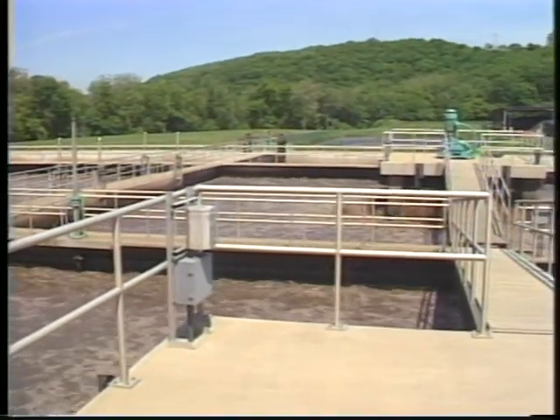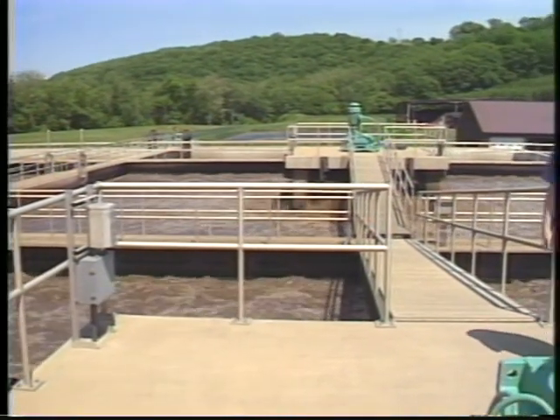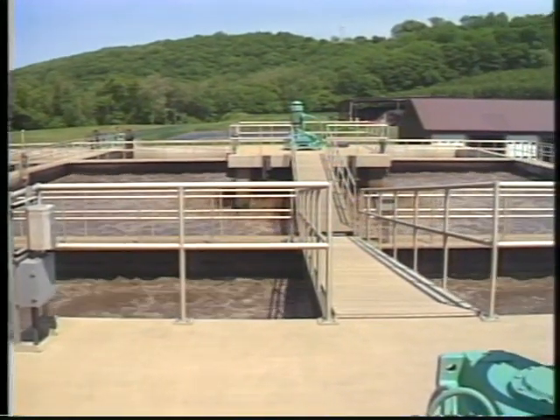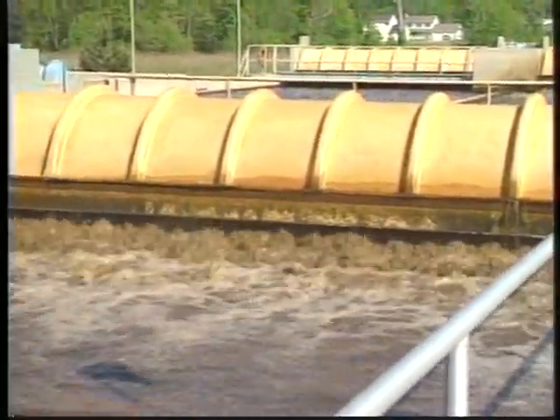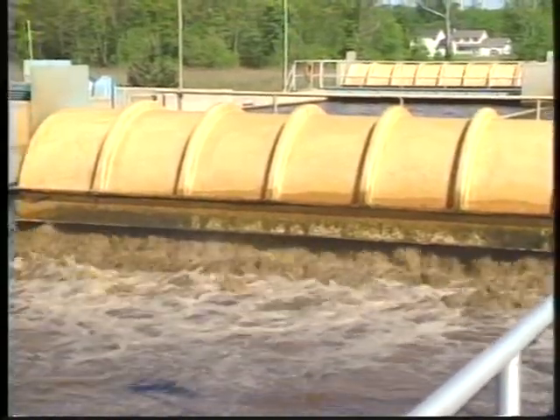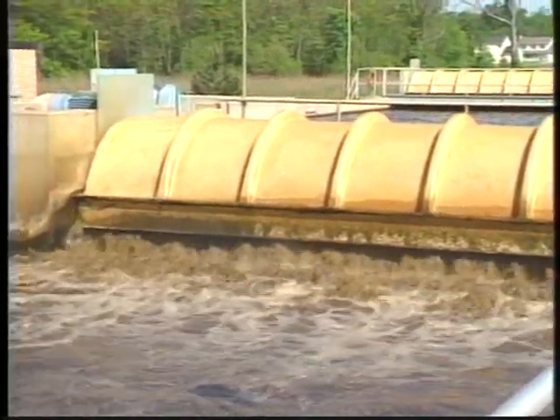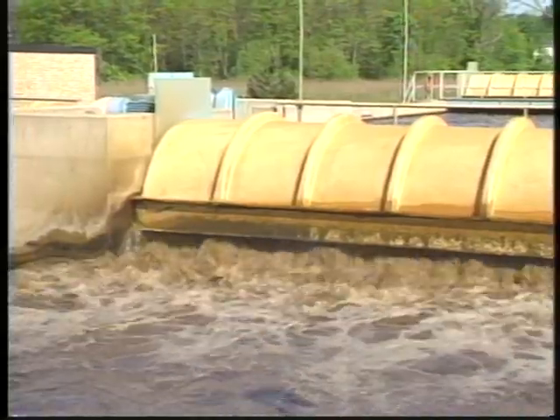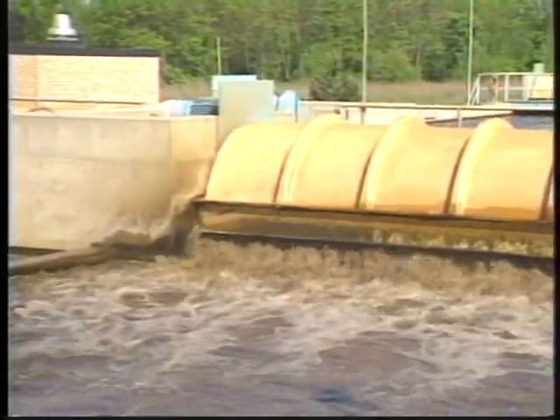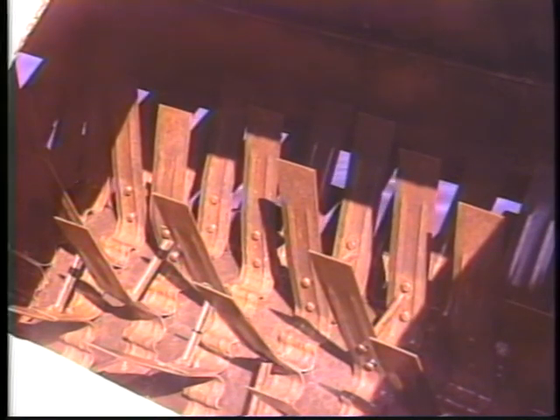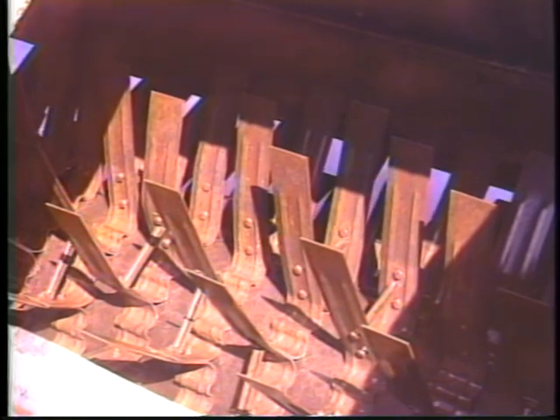With this flexibility, you may be able to treat peak flows or higher loadings at your facility in the contact stabilization mode. The oxidation ditch is another variation of the activated sludge process that is usually operated in the extended aeration mode. This system utilizes a continuous loop type of tank with a rotor. The rotor is a mechanical device that includes a shaft with many paddle-type blades on it.